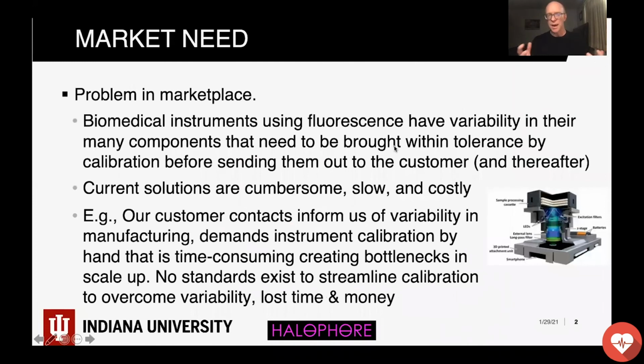So the problem in the marketplace is that as fluorescence-based instruments are manufactured, they have a large amount of variability in the various components that are brought together, from the light source to the optics to the collection camera, that needs to be calibrated to bring that device into tolerance before it is sent out to the customer. And there are also calibration needs once it gets into the customer's hands. The current solutions are cumbersome, slow, and costly.